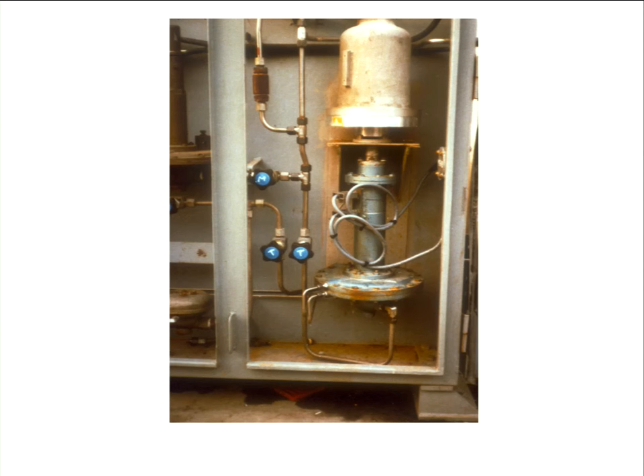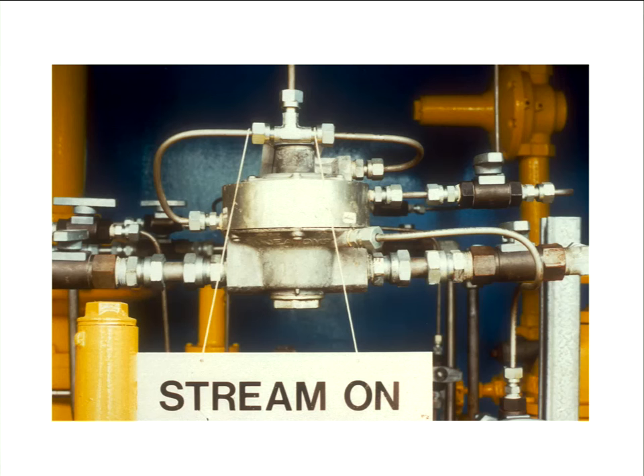This was used, for example, with some district pressure management schemes where you were looking to minimise district pressures to minimise leakage. So you'd have a control system that would perhaps lift this during the peak of the day and the evening peak, and drop it back overnight. But equally, that could just be done on a simple clock type mechanism, something that switches from one setting to another, or there are electro versions of those around as well.